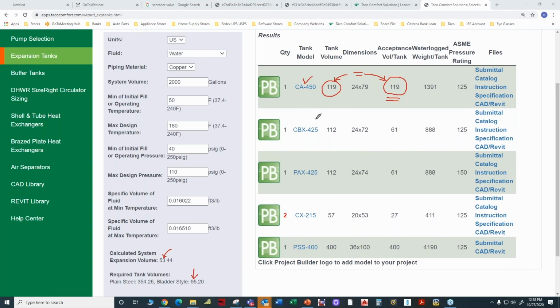Let's look at the second one. Again, we're looking for a steel container that's at least 95 gallons. This one's 112 gallons. In this case, the acceptance volume is 61 gallons. Well, it meets our criteria because we need one that's at least roughly 53 gallons. But in this case, the acceptance volume is less than the tank volume. So we can kind of say there's the tank volume. The tank volume is greater than the bladder. And so that's called a partial acceptance tank.